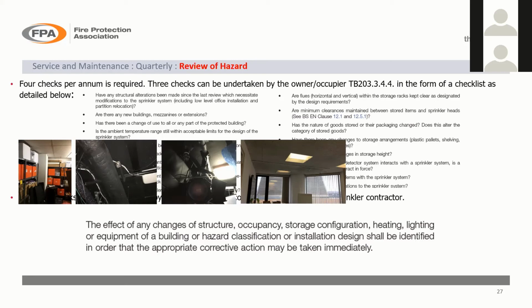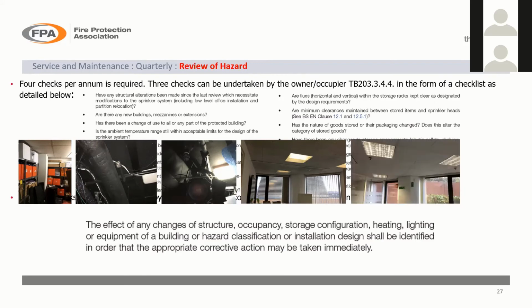So even in an old building that's been there and presumably been insured for a good many years, you still find that the original installation might not have been put in there quite correctly. So we've gone along and done a third-party inspection, flagged that up, and then steps should be taken to relocate those sprinklers into the correct locations.